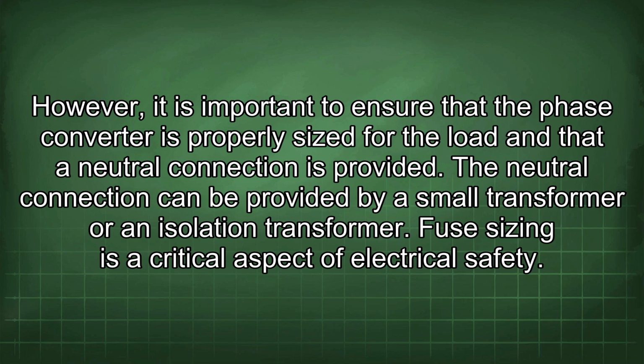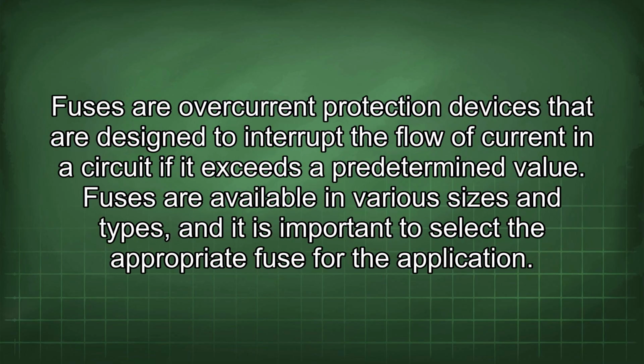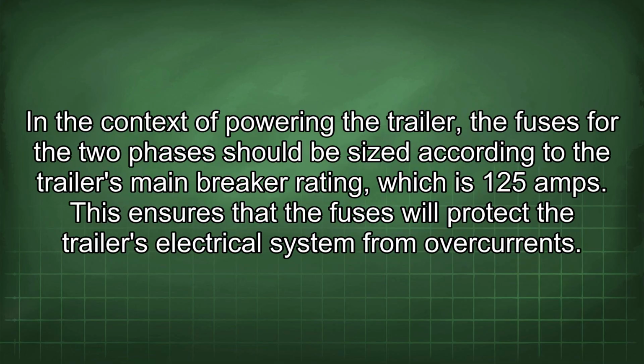Fuse sizing is a critical aspect of electrical safety. Fuses are overcurrent protection devices that are designed to interrupt the flow of current in a circuit if it exceeds a predetermined value. Fuses are available in various sizes and types, and it is important to select the appropriate fuse for the application. In the context of powering the trailer, the fuses for the two phases should be sized according to the trailer's main breaker rating, which is 125 amps. This ensures that the fuses will protect the trailer's electrical system from overcurrent.